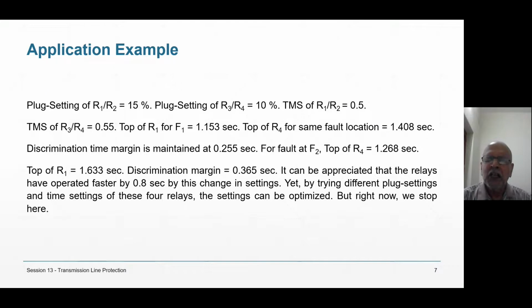So an interconnected system becomes very complex, and therefore relay setting is very complex, and therefore distance protection is used. That is what I wanted to tell you. In plug setting we succeeded at the first iteration. Here we did not succeed at the first iteration. We had to do 10, 15 iterations, which are not shown here. I have shown only the final one in which I have succeeded.